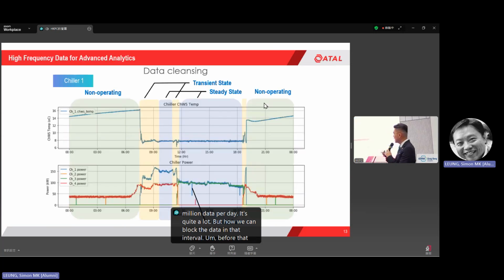Before that, I would like to mention the importance of high accuracy data. You can see that this is the 15-second log data. So you can know that when we switch on the chillers, the cooling time required for our chilled water to reach the set point, we can calculate the cooling time. We can know which data is the transient state data and which data is the steady state. So this is particularly useful for fault detection.